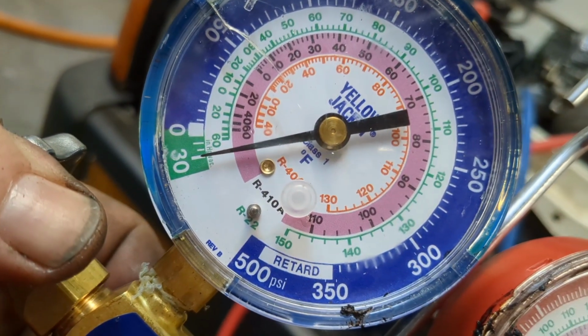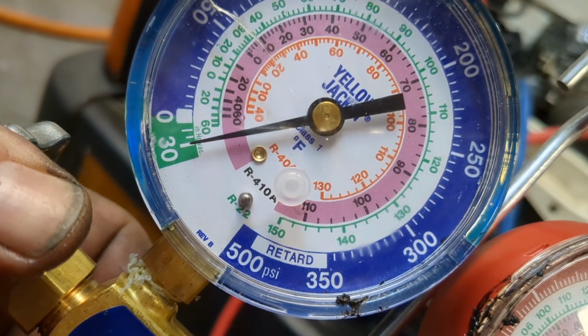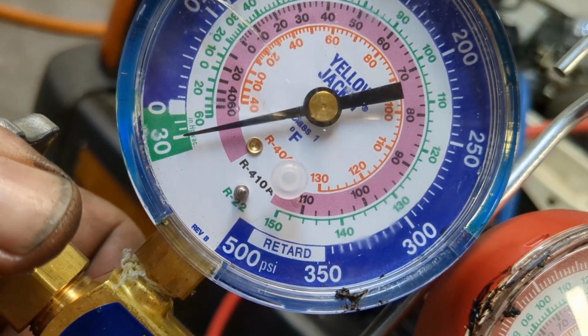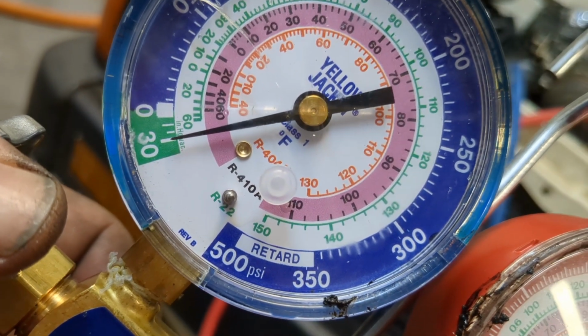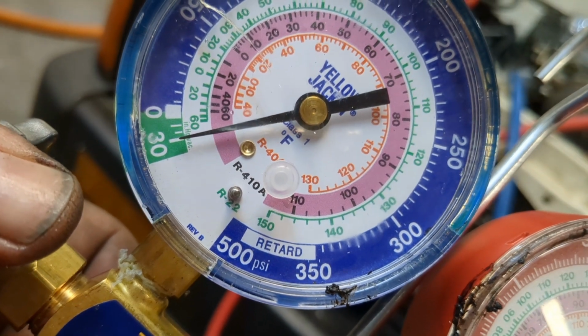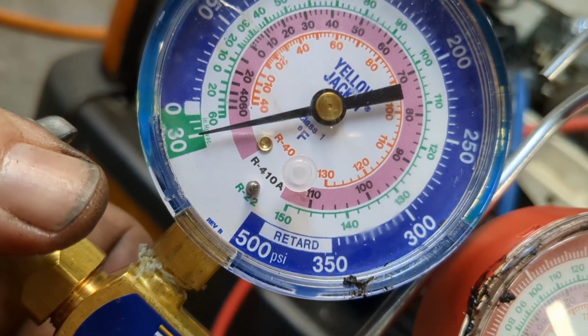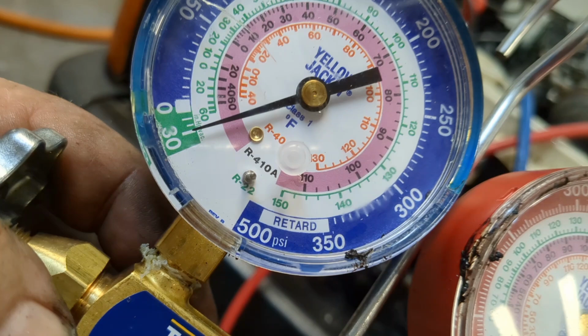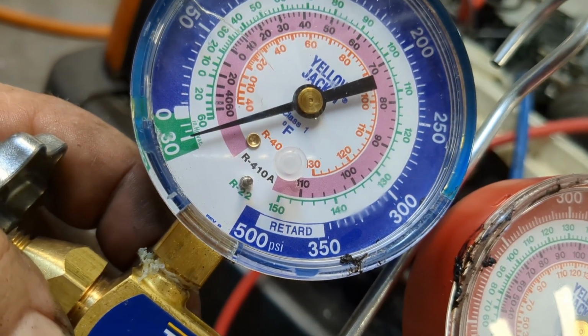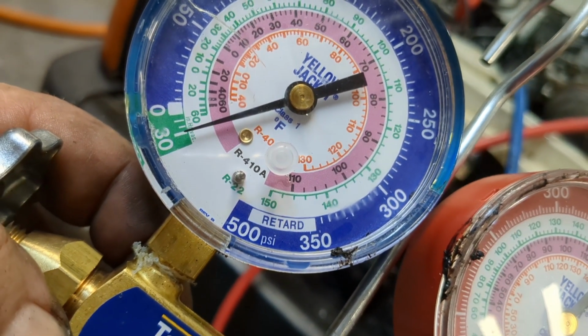So I've got it off, and that needle has not budged a bit, and it probably won't. I'll usually sit here and watch it for 5 or 10 minutes, and if it does not budge, I crack the valve back open. If you hear the least little bit of gurgling in that pump when you crack it open, you probably have a leak. So let's listen for the pump change.